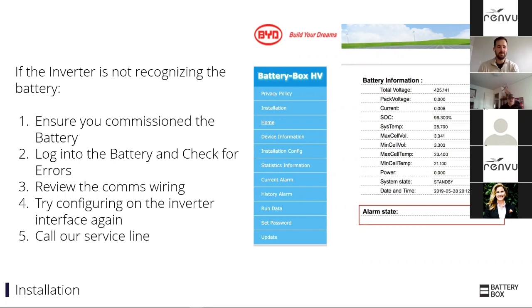One thing to look out for is a common mistake people make when they think they're diagnosing an issue. The brains of the operation is at the inverter, but the battery has a lot of smart features and protections. One of these is an open relay inside, so when you first turn on the battery, it's not immediately giving power to those DC connections going out. If you stack up the battery, turn it on, and take a multimeter reading across these connections, you'll get 0 volts. In our nomenclature, there's total voltage and pack voltage. Total voltage is the internal voltage of the battery, the native voltage of what's going on in the cells. Pack voltage is the voltage applied to the terminals.